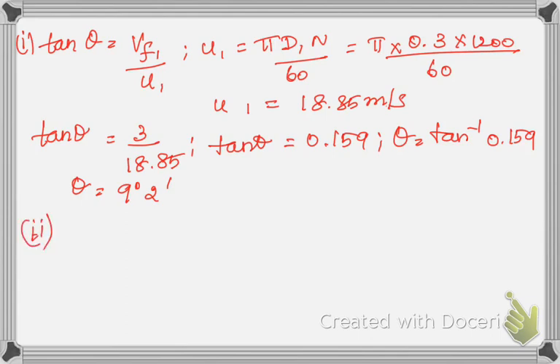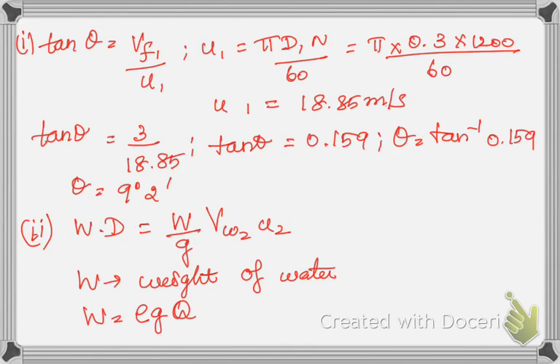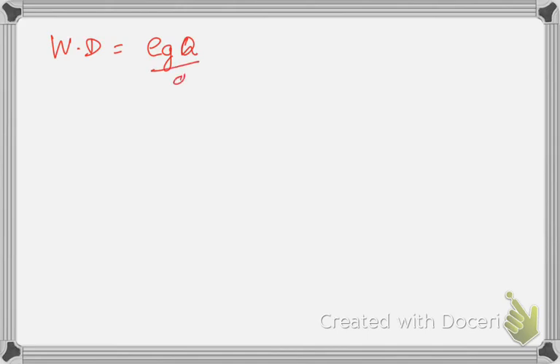For work done, the formula is: Work Done = (ρ g Q / g) × vw2 × u2, where ρ g Q represents the weight flow rate of water, and Q is the volume flow rate. We know ρ and g, but we still need to find Q, vw2, and u2.